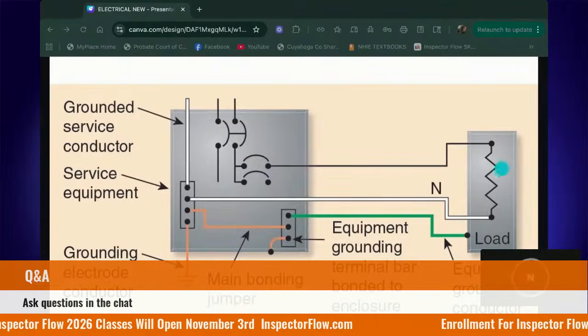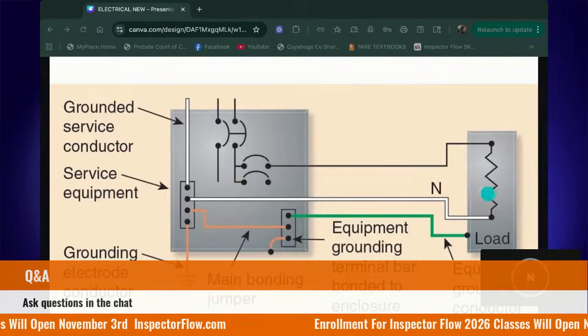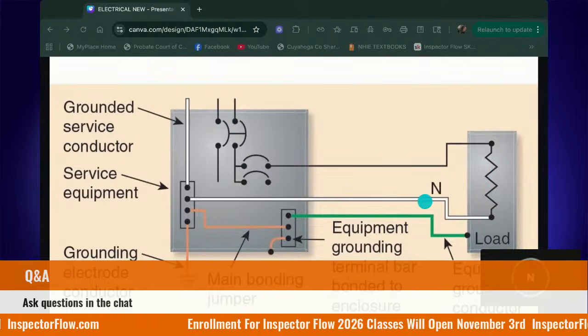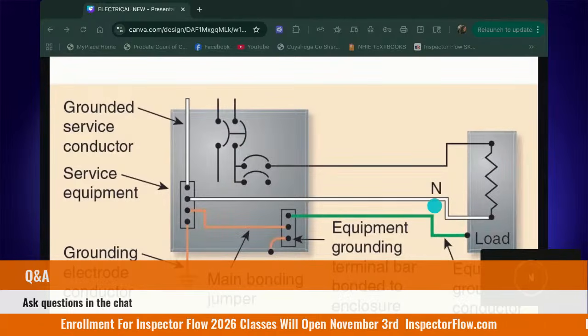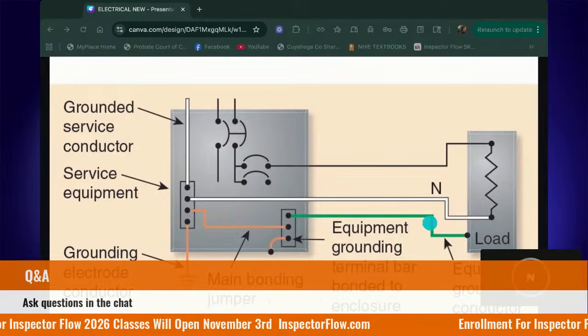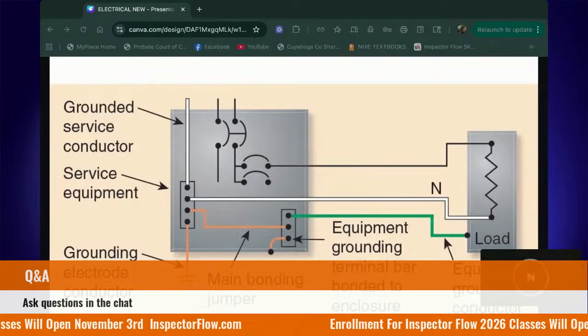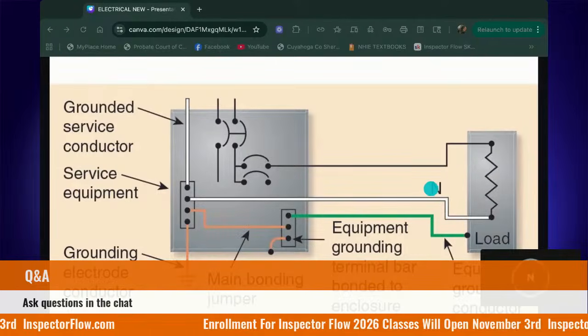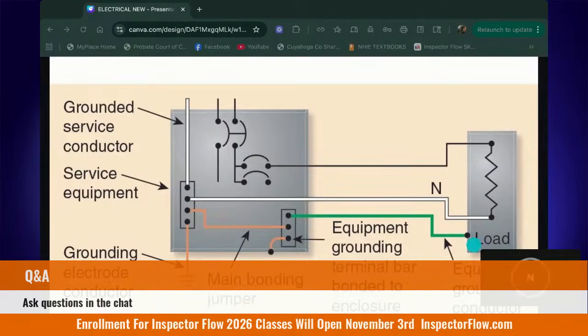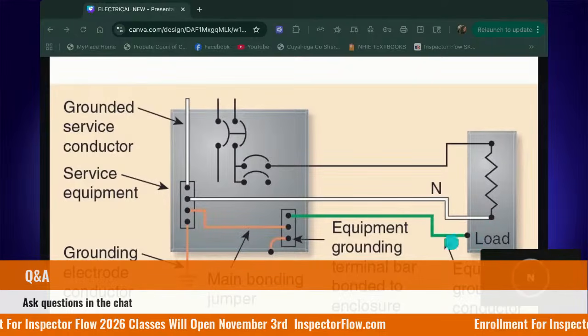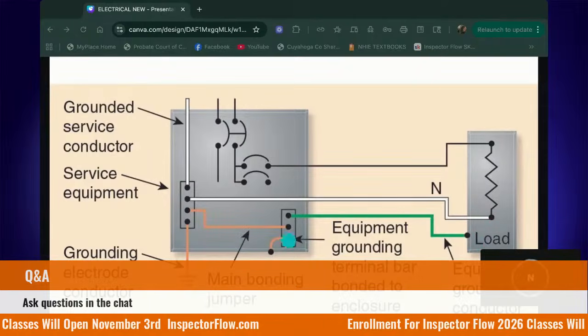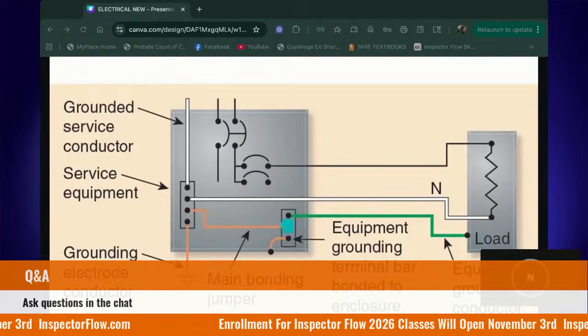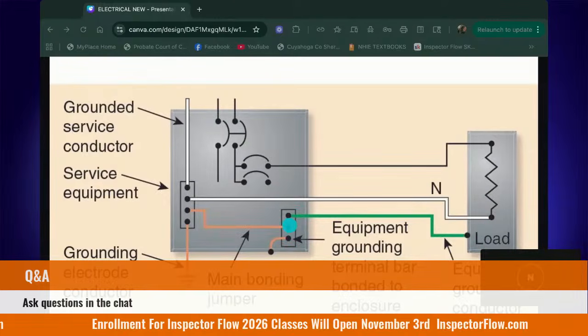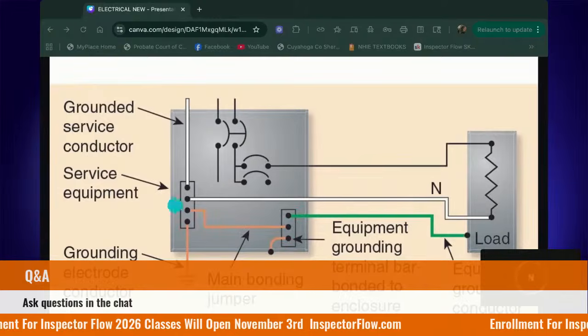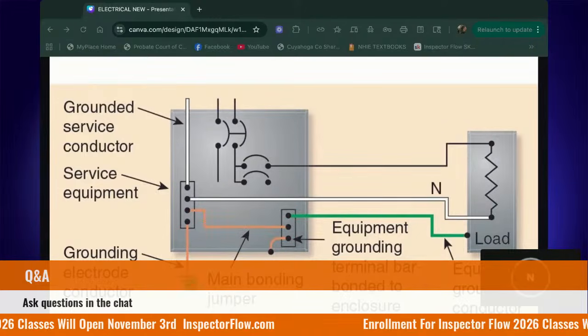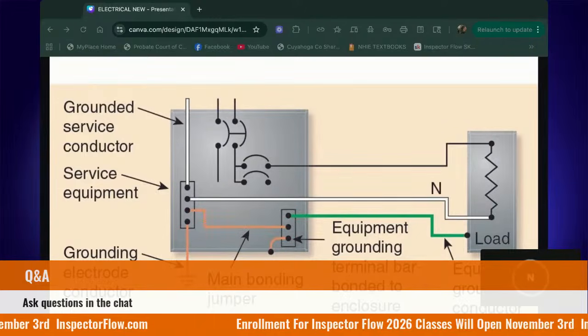The grounding system only carries current when there's a fault or a problem. Say I'm not able to get back via the neutral. I need to travel now as an alternate path because it's going to keep traveling. Something is going to get energized. Okay. So now I'm traveling on the grounding system, terminating to the grounding bar here in the panel, which is connected to the neutral bus bar, which is connected safely to ground outside.